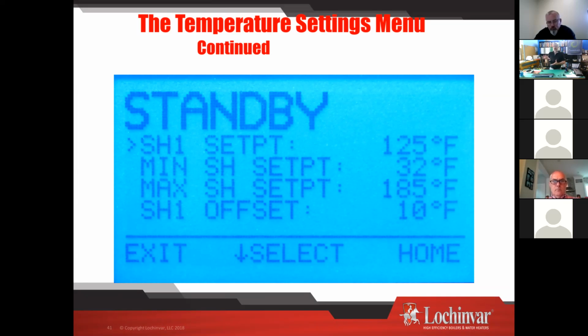We all know that you put this in, the homeowner's going to be excited, the facility guy's going to be excited, whatever it is. And they're like, hey, I'm going to go down and touch the control and make an adjustment without knowing it. And all of a sudden they've set their space heat set point to 60 degrees. Then they call up, I got no heat. So you may want to look at, hey, what's the minimum temperature I'm ever going to let this boiler go? There's your minimum set point. Set that. The homeowner or whoever can't go below it, prevents a callback.